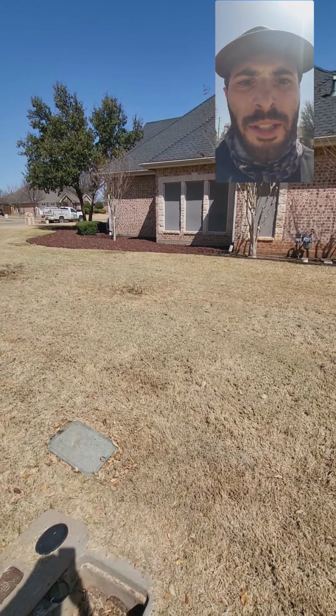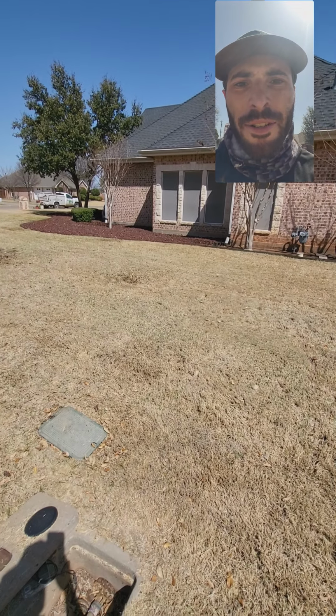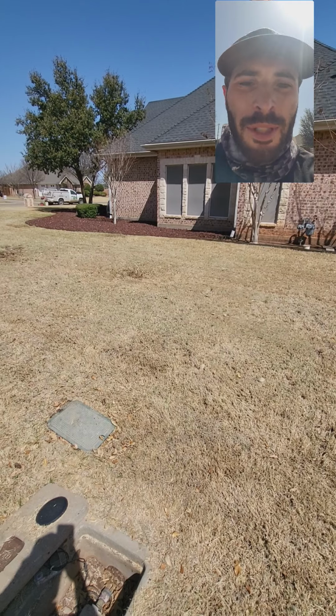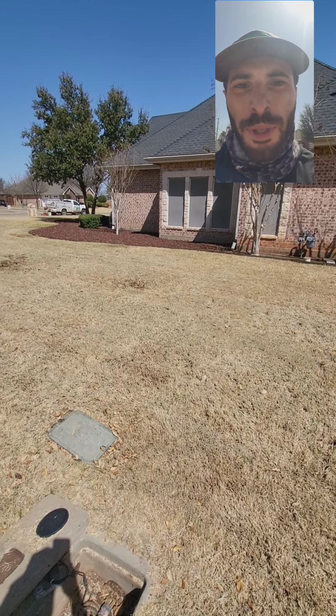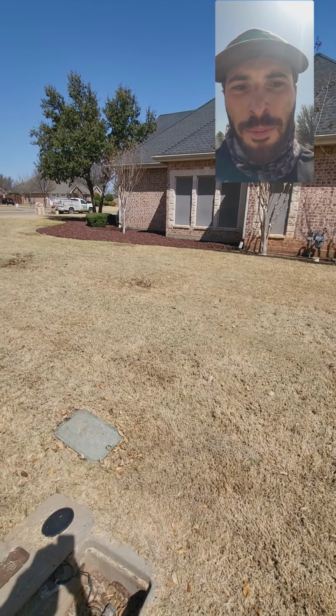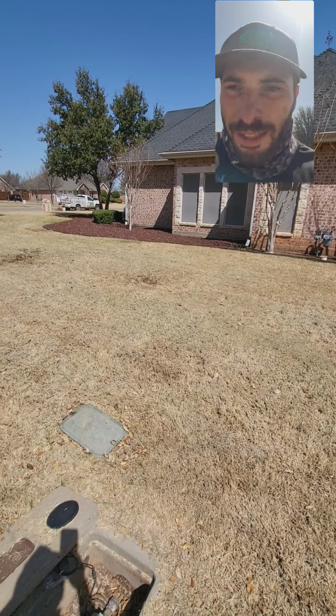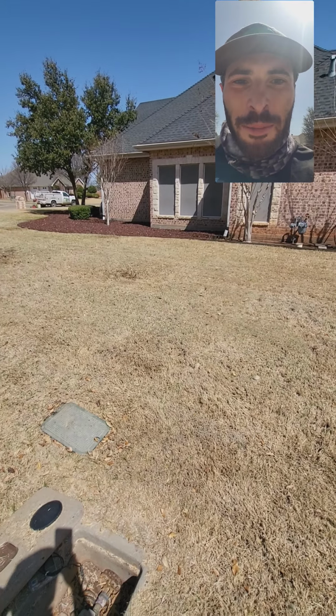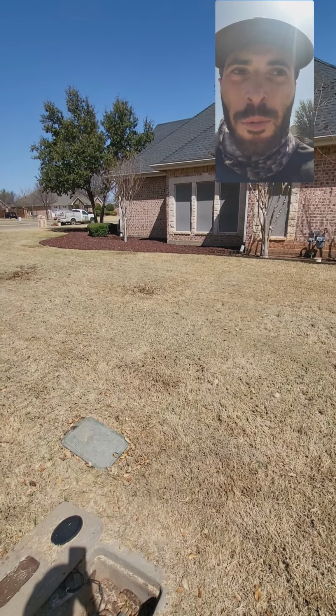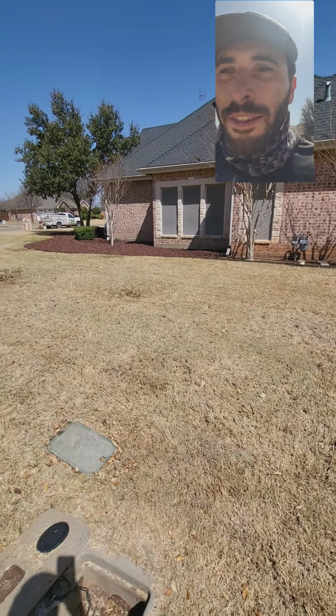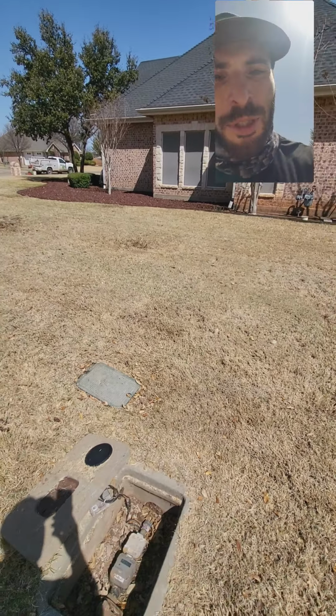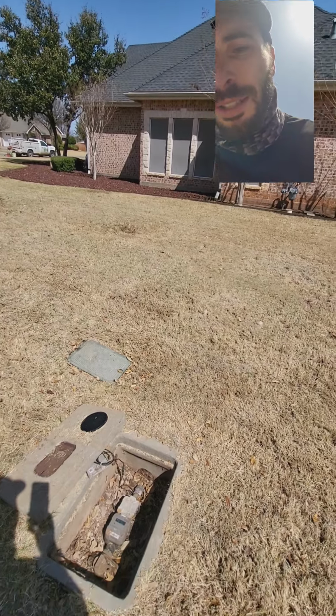So this video is on how to test to see if there is a leak or a stuck valve or just any type of water moving through the sprinkler system. Now keep in mind, this test is only going to work if the system is running off of the city water. If this is operating off a well, then this method is not going to work, but the majority of the time it is going to be working off a city. So this is what you do.